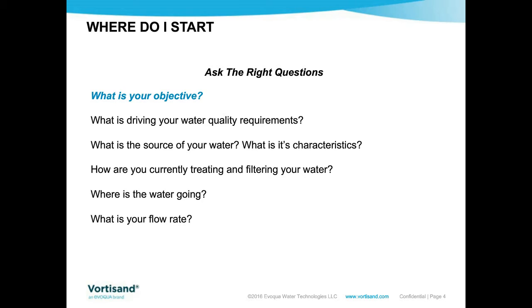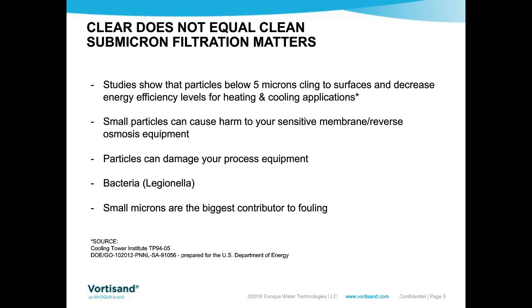Let's talk a little bit about what's in your water, because that's very important too. Did you know that your eye can only see particles of about 50 microns? Well, that's pretty small, but you know, for a membrane, this is huge. So when you look at the fine stuff, peer-reviewed studies show that particles that are really fine, below 5 microns, they tend to cling to surfaces. And in heat exchange applications, they tend to reduce the heat transfer efficiency. The small particles also can cause harm to membranes.